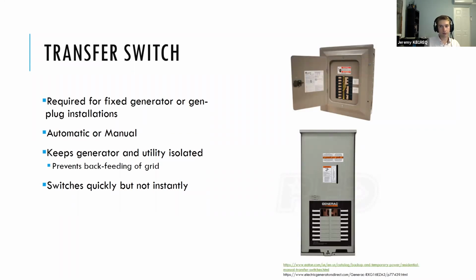So a transfer switch is an important part of a fixed or gen plug installation. What this does is keep your generator isolated from the utility. That's important for the safety of the electric utility workers, because without this, there's the ability to backfeed from your generator onto the electrical grid. And that can be deadly for the electrical workers when electricity essentially shows up where they're not expecting it. So there are two types of transfer switches: automatic, which is designed to work with a fixed generator, and manual, which is designed to work with a gen plug.